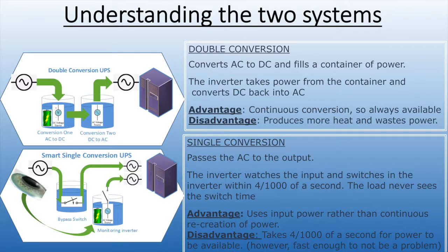There are two types of UPS systems: double conversion and single conversion. In double conversion, all of the energy reaches the load, as shown in the upper picture, by taking power from the grid, converting it to DC, then reconverting it back to AC before delivering it to the load. This is done so that when power goes out, it's always being converted, meaning there's never a flinch or downtime in power.